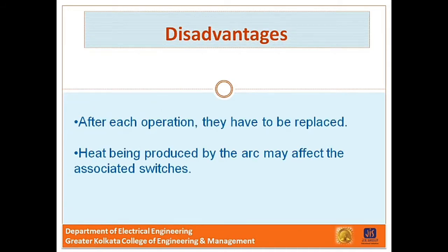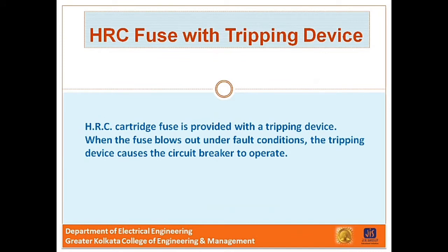And what are the disadvantages? Now they have to be replaced after each operation. And the second disadvantage is heat produced by the arc may affect the associated switches. Next one is the HRC fuse with tripping devices. Now sometimes HRC cartridge fuse is provided with a tripping device. Now when the fuse blows out under fault condition, the tripping device causes the circuit breaker to operate.